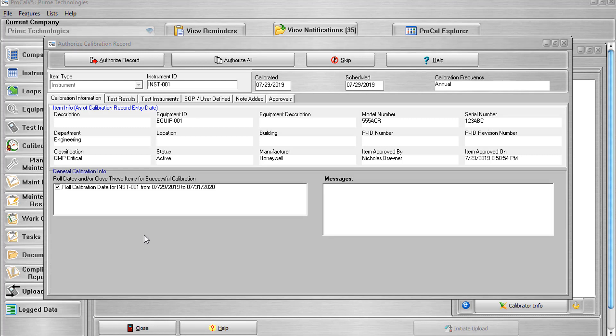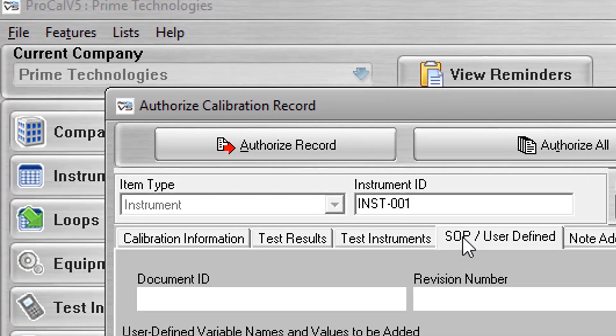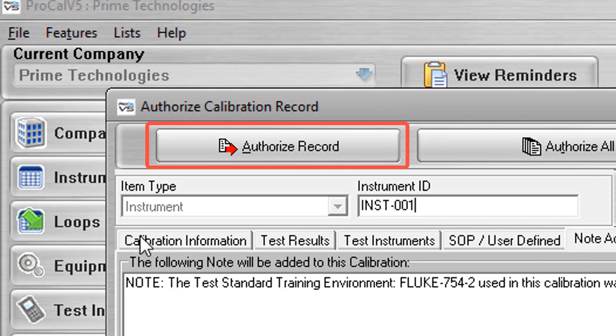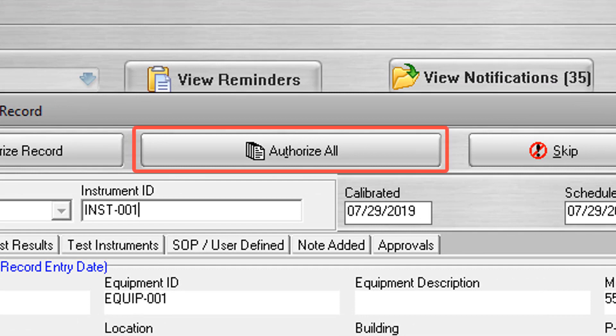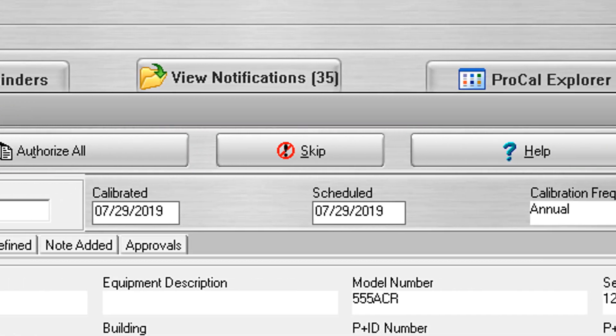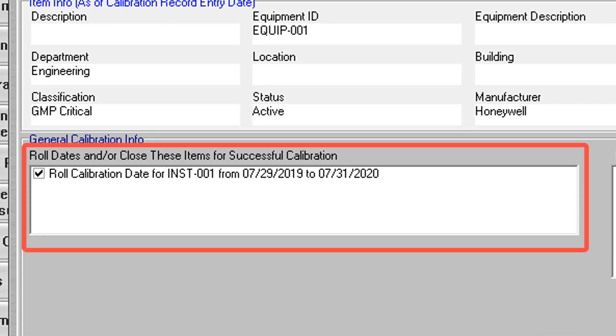ProCal V5 contains a special feature that allows you to authorize or skip each calibration result uploaded from the device through the Authorize Calibration screen. The information you see as you navigate the tabs is what will be used to create the calibration record once authorized. Selecting the Authorize Record button will add the calibration currently displayed to the software as a calibration record, and all indicated date rolling and item closing will be performed. The Authorize All button will add an entire upload session as multiple calibration records. Selecting the Skip button will skip the current calibration — nothing will be uploaded and no changes are made to the database. This is useful when uploading more than once from a single calibrator and the user has already created the current result as a calibration record.